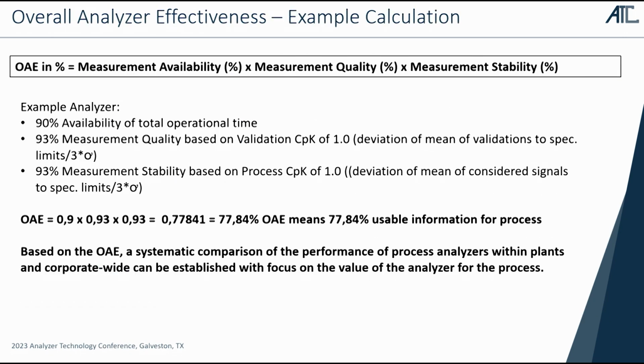All this information influences the overall analyzer effectiveness, which describes the performance of the analyzer. So in the end, if you have 90% availability of your analyzer and you're tracking the KPIs for validation and stability of the measurement, you might have a validation and a process CPK of maybe 1, which is actually not so good, to be honest.